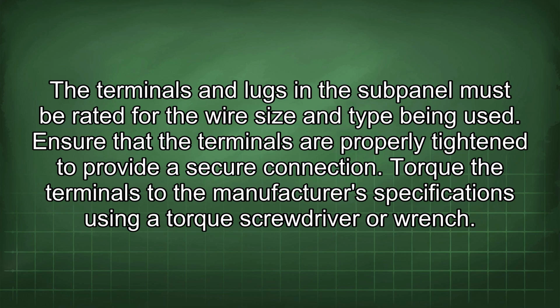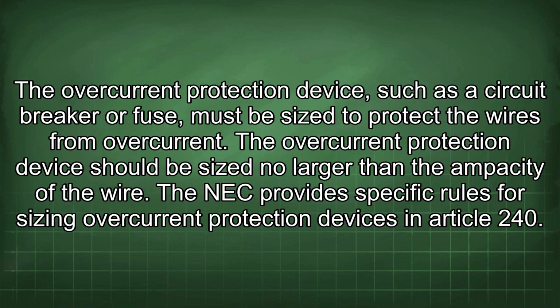Ensure that the terminals are properly tightened to provide a secure connection. Torque the terminals to the manufacturer's specifications using a torque screwdriver or wrench. The overcurrent protection device, such as a circuit breaker or fuse, must be sized to protect the wires from overcurrent. The overcurrent protection device should be sized no larger than the ampacity of the wire. The NEC provides specific rules for sizing overcurrent protection devices in Article 240.